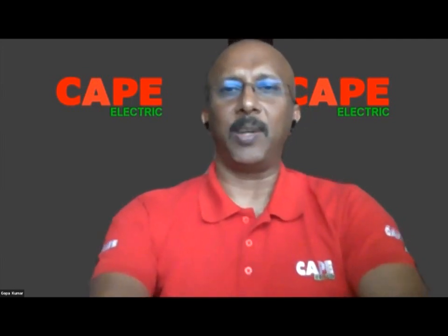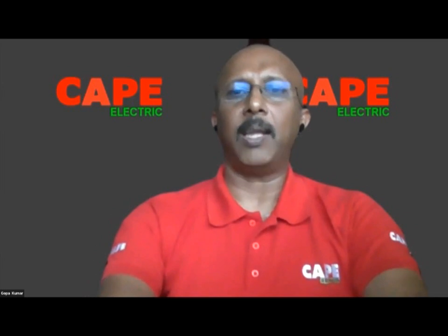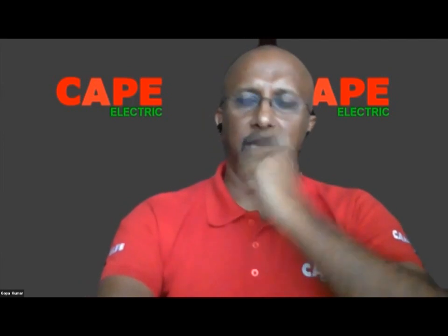How is the earth conductor sizing defined? If you look at clause 5.4 of the standard, explaining it over a program will be very difficult. There are several parameters we need to consider to size the earthing conductor. As I said, there are three types of conductors: protective earth conductor, protective bonding conductor, and earthing conductor. The earthing conductor is the one which goes to the earth electrode. The protective earthing conductor and the protective bonding conductor are inside your building.